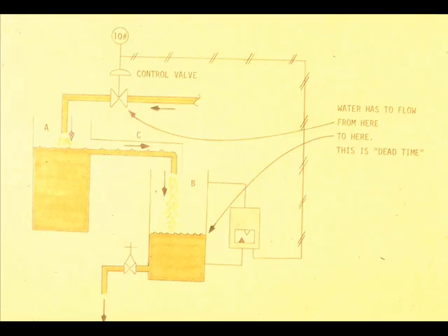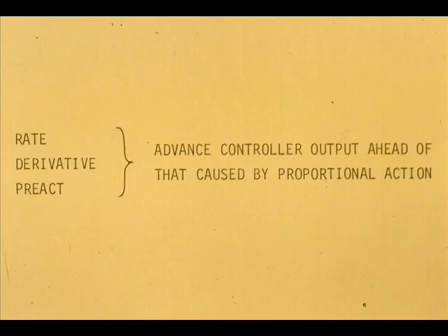Some control loops, having lags and dead time, can be better controlled if the control valve position is advanced beyond that caused by proportional action. Rate, derivative, or pre-act will perform this feat.